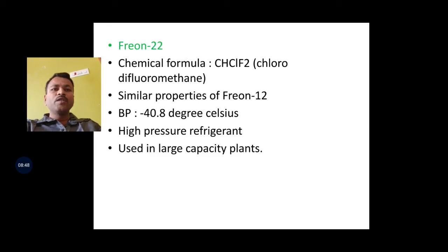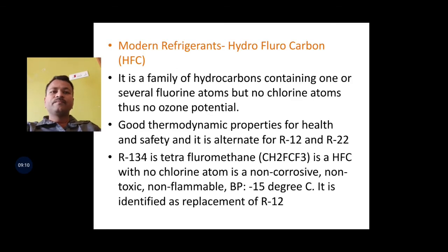Next, Freon 22. Its chemical formula is CHClF2, chlorodifluoromethane. It has similar properties to Freon 12. Whatever properties Freon 12 has, Freon 22 also has the same. The boiling point is minus 40.8 degrees Celsius. It is a high pressure refrigerant, used in large capacity plants.